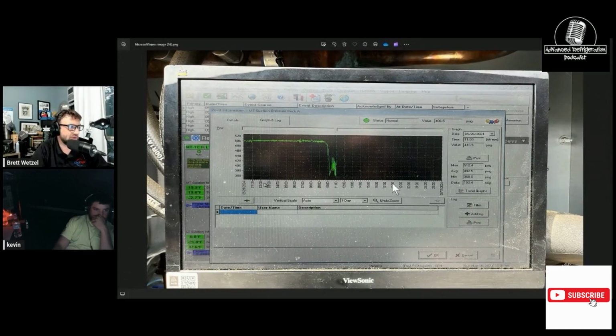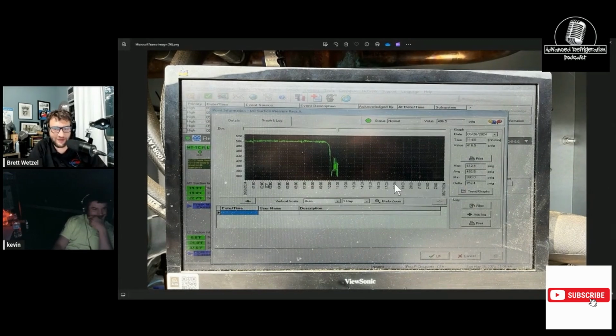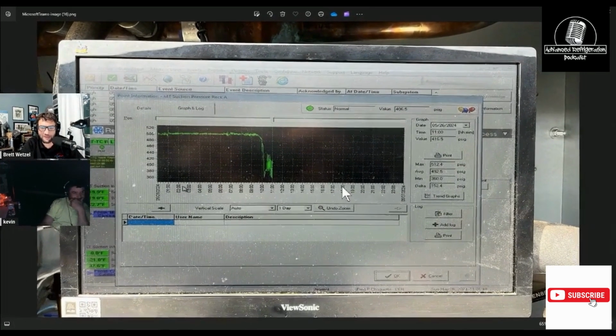So here you can see the suction pressure, and then you can see the superheat. And then once it started dipping down below the no zone, like below 18, I think actually, yeah, it was set for 18, which I don't understand why it's set for 18. That doesn't make any sense, because if they're a minimum of 20 degrees of superheat, like on the transcritical side and the medium temp side, I don't understand why you wouldn't clear the no zone. Yeah, you can keep laughing at me.